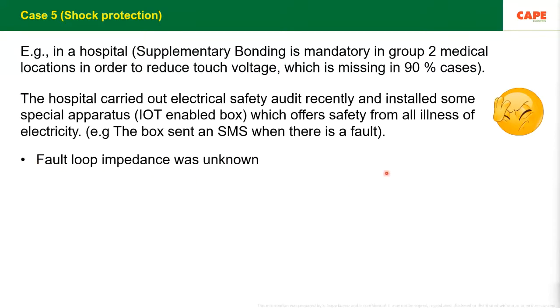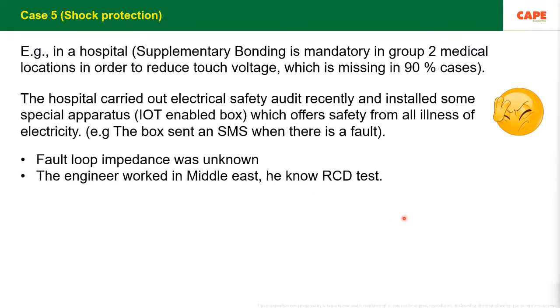Then for this particular engineer, of course, fault loop impedance was a little bit unknown. But this engineer or supervisor had worked in the Middle East. Then I asked, have you carried out the RCD test? Because the RCD test is quite mandatory in the Middle East. Then he told me, no, we didn't. Then I asked, okay, did your electrical auditor do the RCD test? No, the electrical auditor also didn't do the RCD test.